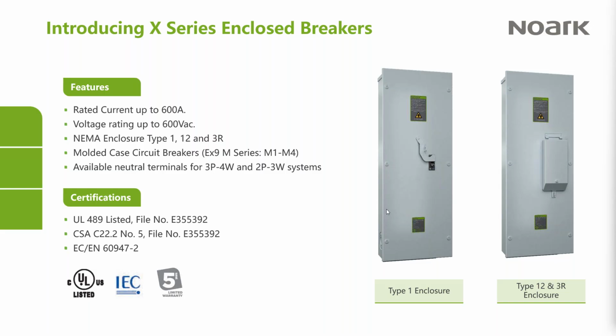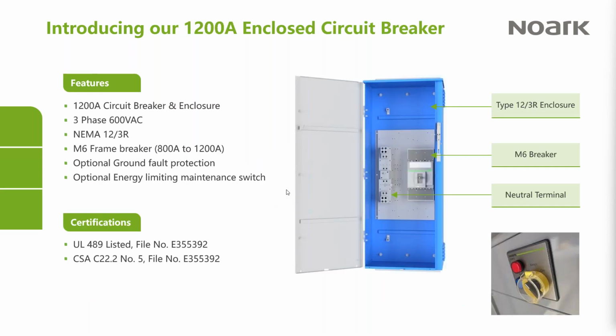All of our enclosures have neutrals available, which I'll be showing you in a lot more detail. Rob, I do believe you're going to be addressing this coming up, but I did just get a question while you're looking specifically at that breaker: can you get a shunt trip with these enclosed breakers? Yes, any of the accessories that we offer in the standard breaker line can be included in an enclosed breaker. Now, I've got to qualify that, because what I mean is all of the internal accessories. So shunt trips, undervoltage releases, auxiliary contacts, all of those internal accessories are perfectly fine to add into an enclosed breaker. External accessories, such as the motor operator, add a significant amount of depth to the breaker and motor operator combination, so it doesn't fit inside the enclosure.